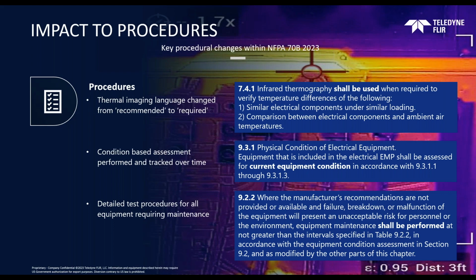So pointing out here that infrared thermography shall be used when required to verify temperature differences, through two components: similar components under similar loading, and comparisons between electrical components and ambient air temperatures. Those are two acceptable means by which to perform the comparisons. An important point of note is that when we consider loading requirements, the NFPA guidance does suggest those components need to at least be under...